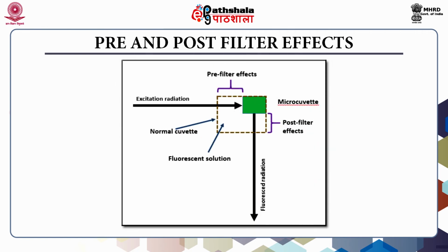Pre-filter effects arise due to the absorption of radiation before reaching the fluorescent molecule, and post-filter effects arise due to the decrease in fluorescence emitted by the fluorescent molecule before escaping the cuvette. These effects increase with the increase in sample concentration.